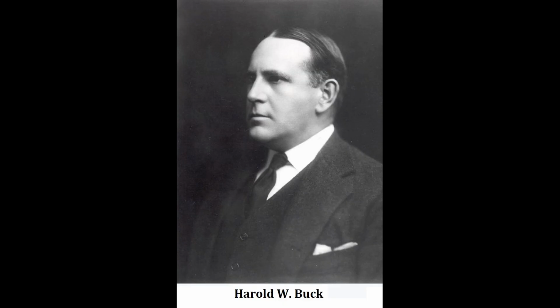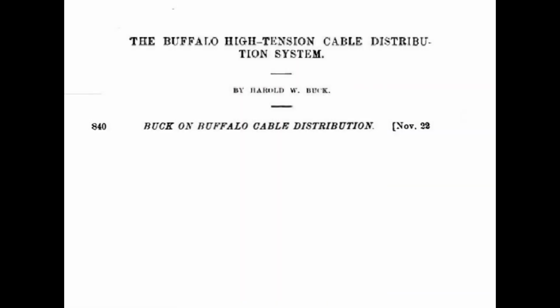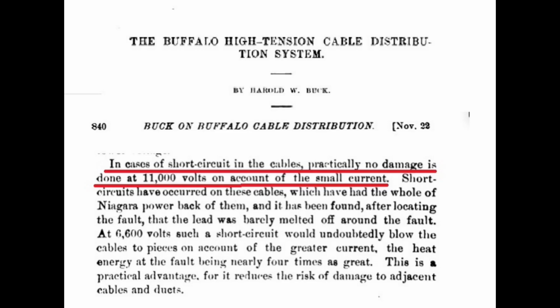Harold W. Buck, an eminent electrical engineer and former president of the American Institute of Electrical Engineers, who in 1894 graduated from Yale University, wrote about short circuits in the 1901 AIEE transactions. "In cases of short circuits in the cables, practically no damage is done at 11,000 volts on account of the small current." He continues, "At 6,600 volts, such a short circuit would undoubtedly blow the cable to pieces on account of the greater current." He appears to be confusing the short circuit situation with that of the constant power concept when dealing with the transmission voltages.